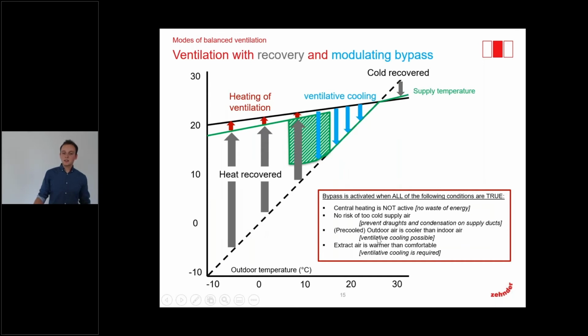The bypass is activated when all of the following conditions are true. The central heating is not active, so that we do not waste energy. There is no risk of too cold supply air, to prevent drafts and also to prevent condensation on the supply ducts. The outdoor air is cooler than the indoor air, so ventilative cooling is possible at all. And last but not least, the extract air is warmer than comfortable, so ventilative cooling is required.